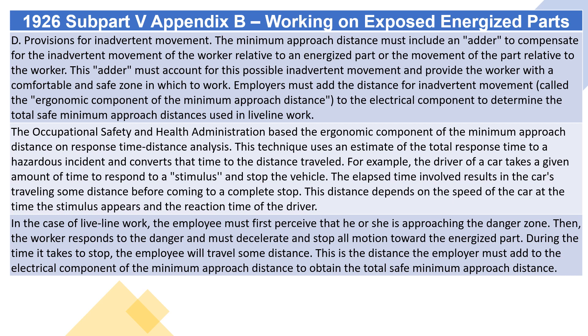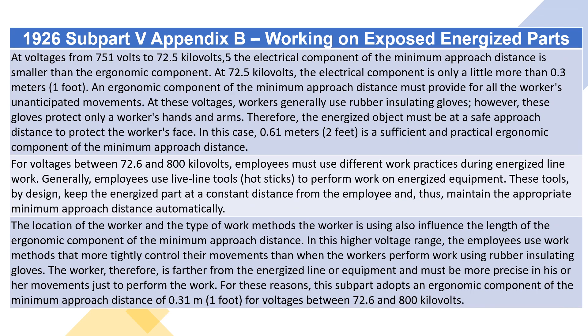At voltages from 751 volts to 72.5 kilovolts, the electrical component of the minimum approach distance is smaller than the ergonomic component. At 72.5 kilovolts, the electrical component is only a little more than 0.3 meters (one foot). An ergonomic component must provide for all of the workers' unanticipated movements. At these voltages, workers generally use rubber-insulating gloves; however, these gloves protect only a worker's hands and arms. Therefore, the energized object must be at a safe approach distance to protect the worker's face. In this case, 0.61 meters (two feet) is a sufficient and practical ergonomic component of the minimum approach distance.